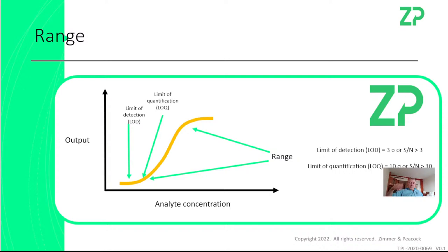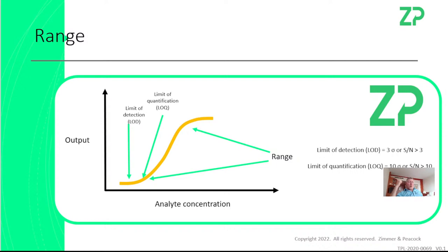Sensors have upper ranges too. With most immunosensors there's something called the hook effect — you can add more and more analyte and at some point the signal will stop changing. It's the same with enzymes: there's a point at which there's not enough enzyme to keep up with the amount of analyte. The upper range is often proportional to how much detection molecule I have on that sensor. The lower limit of detection is often based on how precisely I manufacture that sensor.